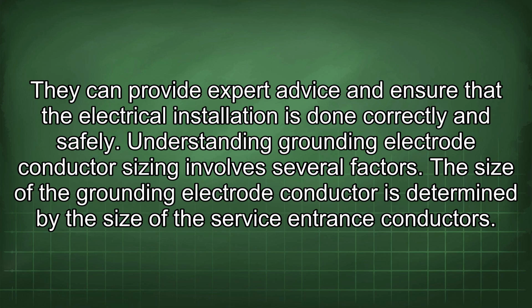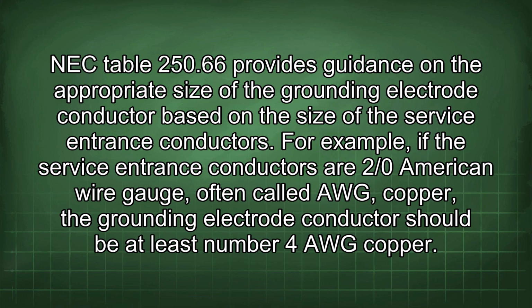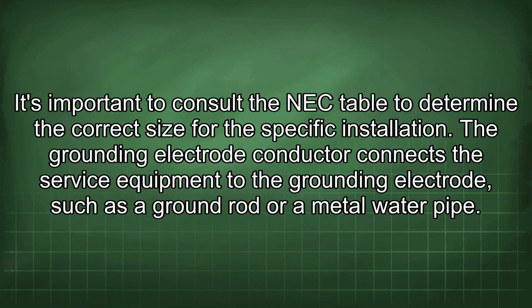Understanding grounding electrode conductor sizing involves several factors. The size of the grounding electrode conductor is determined by the size of the service entrance conductors. NEC Table 250.66 provides guidance on the appropriate size of the grounding electrode conductor based on the size of the service entrance conductors. For example, if the service entrance conductors are 2/0 American wire gauge, often called AWG copper, the grounding electrode conductor should be at least number 4 AWG copper. It's important to consult the NEC table to determine the correct size for the specific installation.